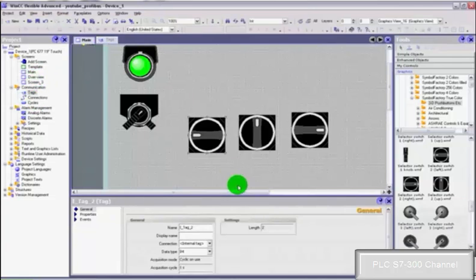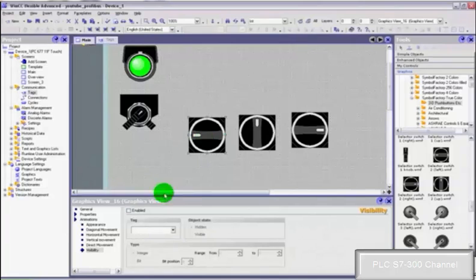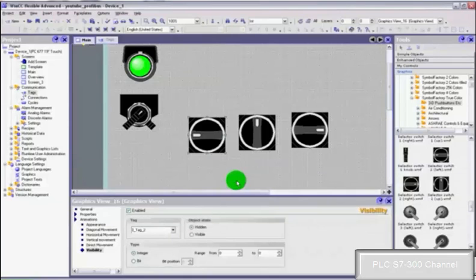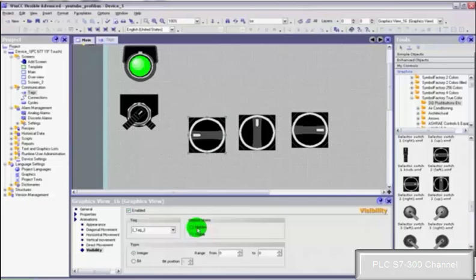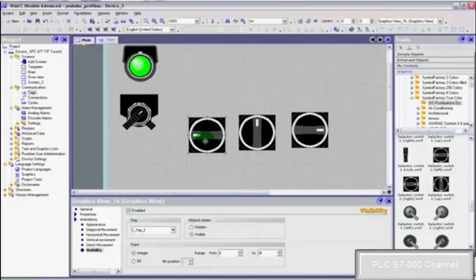We go back to our screen. Select the first graphic, visibility, click enabled and select our integer value which is tag 2. Keep that selected at integer. Click the visible and the range is 0 to 0. So in other words when this value is in the range of 0 to 0, just 0, then that will be visible.